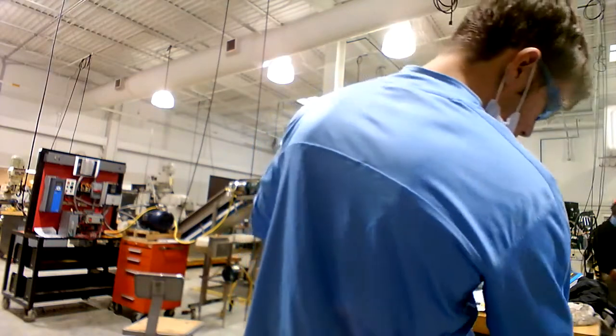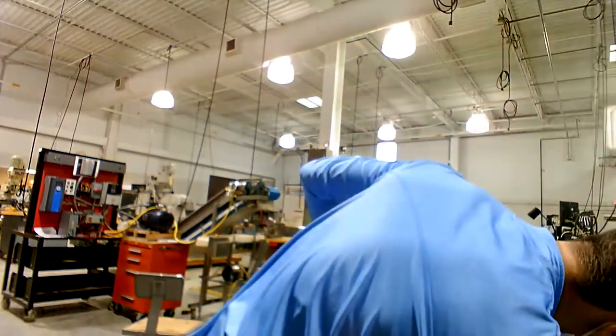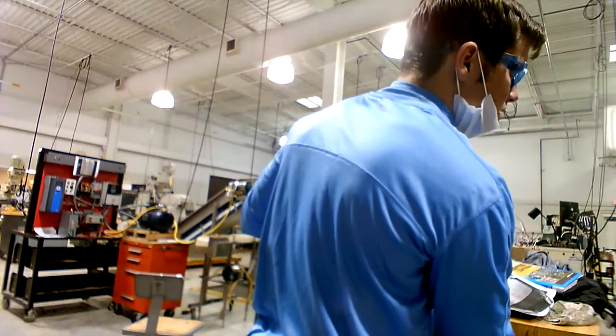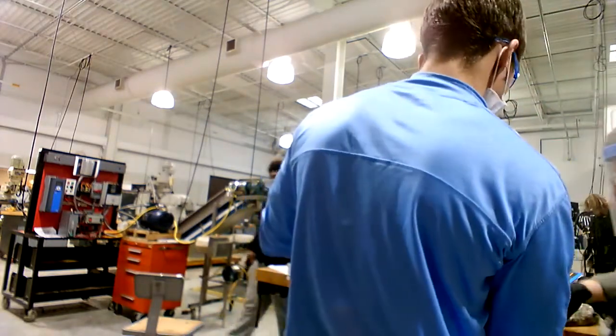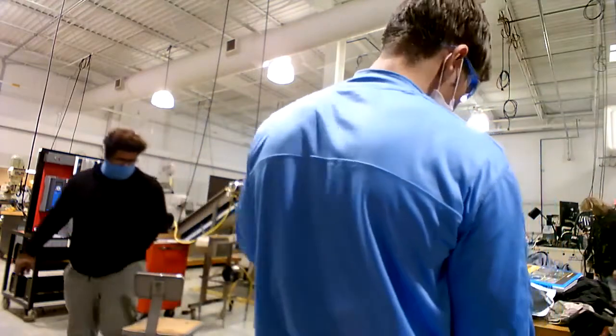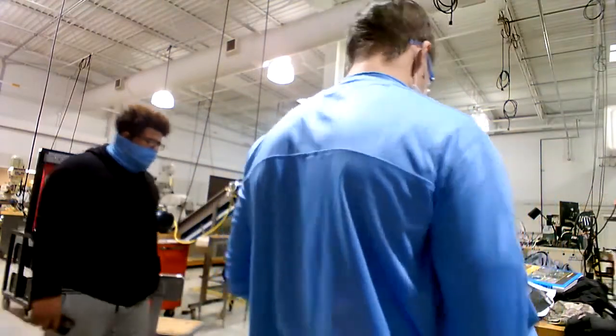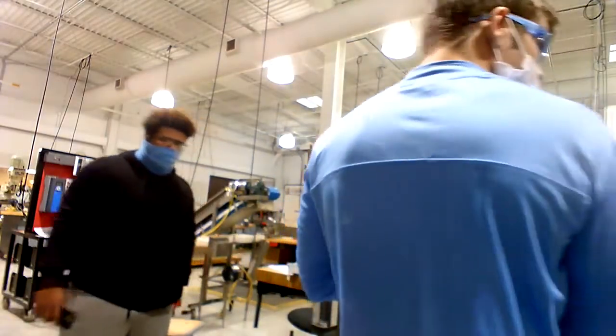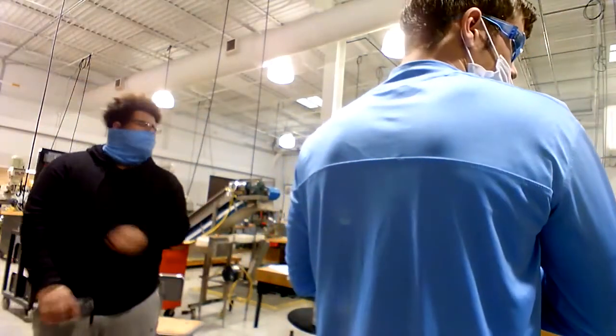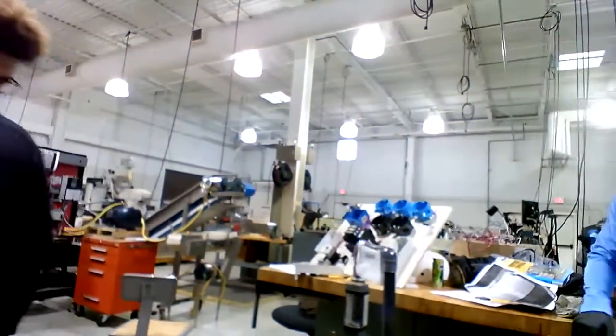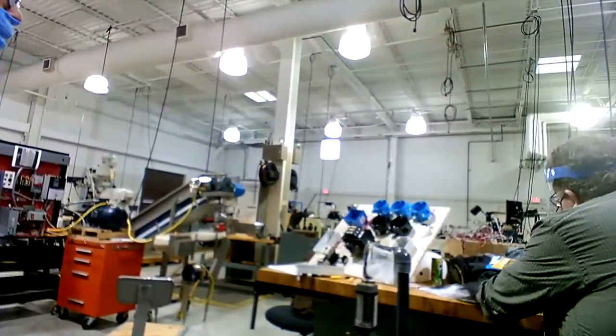This is ready to run. The incoming sources, it honestly doesn't matter which you connect to. That motor will run the same, it'll run the same direction clockwise, it doesn't matter, because it's single phase. On three phase, if you flip either two of the three hots, the motor will go the other way. For this, to make it go the other way, you're gonna do the run winding.